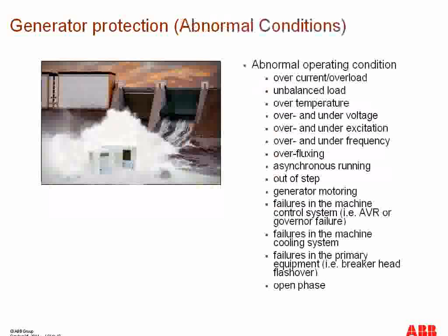Then there can be several abnormal conditions which can impact generator protection. Those abnormal conditions can be overcurrent and overload conditions, unbalanced load, over temperature, over and under voltage conditions, over and under excitation conditions.